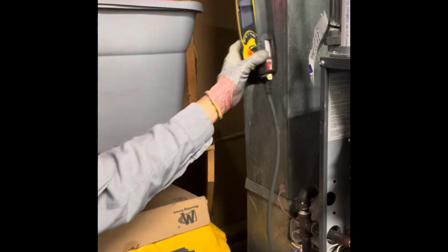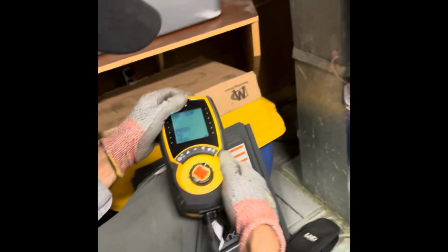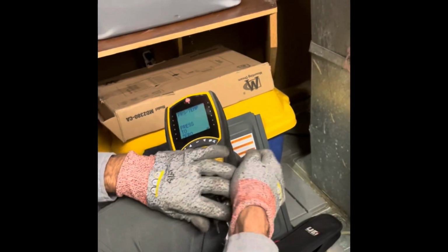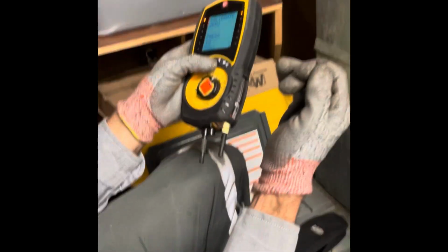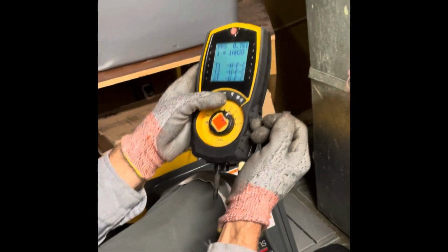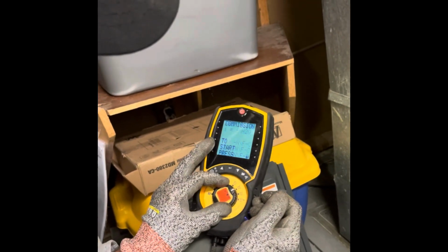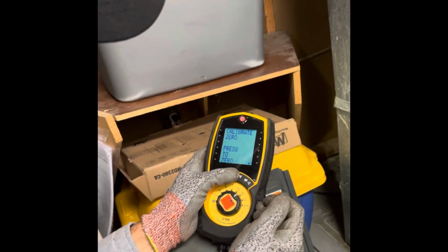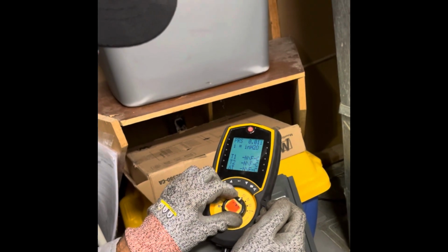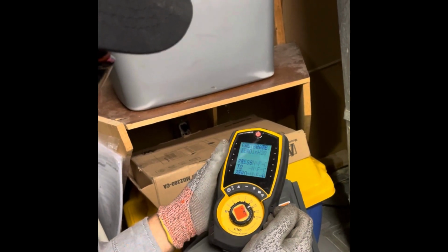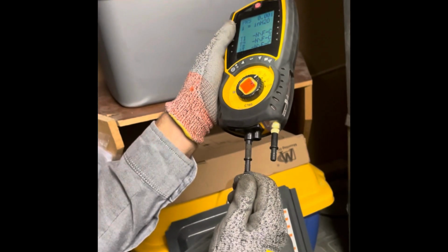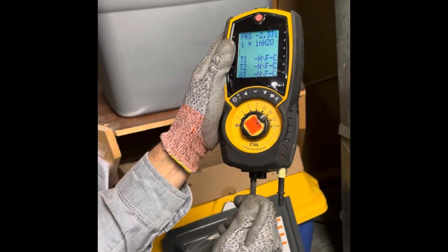So gas pressure, I'm just going to tare this back to 0. So give me 1 minute. So I'm pinching the line so that I'm not releasing gas. I'm not at 0 yet, so I'm just going to keep bringing this down, calibrate it till I hit 0. Okay, so now my pressure is going to be accurate on the measurement I'm getting.